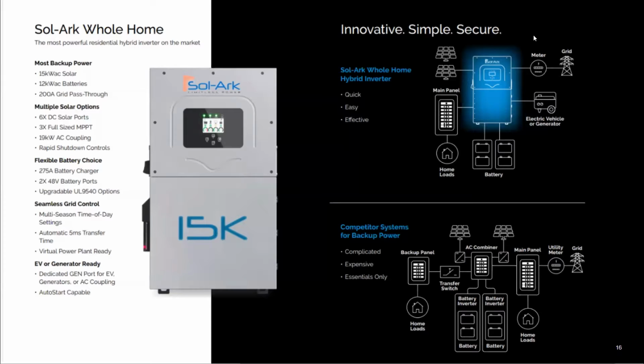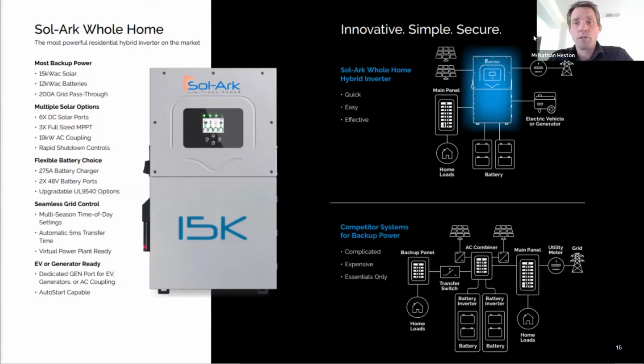And load control is sometimes perceived as necessary to stay within the output limits of the inverter system. But what I would say is, if that's a concern, then you should be starting with the largest inverter possible, which the 15K is. It does 15K with solar, 12K AC without solar. And what you mentioned, John, is what I liked so much about installing a 15K. You don't have so many parts and pieces. It's a quick, easy install, and yet you have a lot of power to integrate multiple things, even smart loads, right? Two-wire start with generators we'll get into.